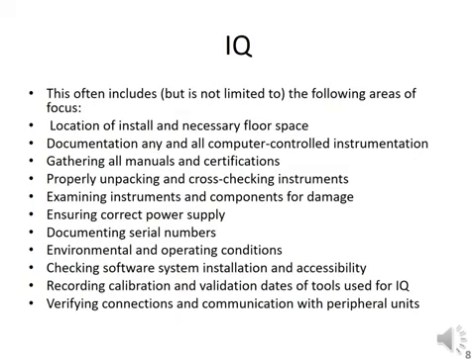Environmental and operating conditions, these are important. Whatsoever is given in the manual or the operating conditions or SOP, you have to fulfill and maintain those conditions. Checking the software system installation and accessibility: the software system associated with your equipment should be installed properly along with the machine, right? And that should be accessible. Okay. Recording the calibration and validation dates of tools used for IQ. Whenever you are calibrating it, installing it, or validating it, you have to keep the record of all the dates.